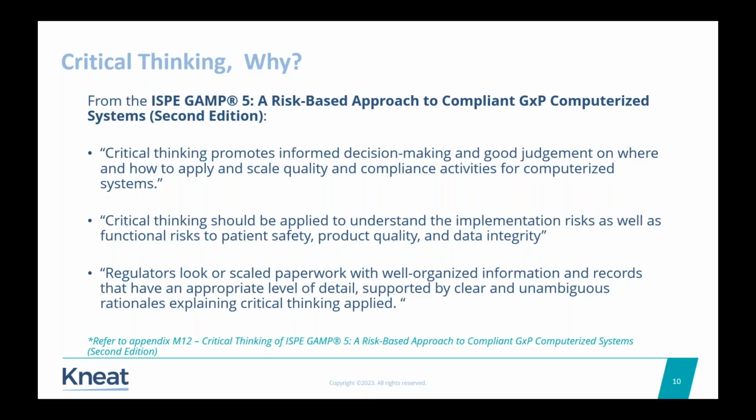Essentially, what this means is that you have thought about the process that this particular software system is going to help you implement. Where are the riskier parts of the system? How did I determine that this is a high risk feature or this is a high risk system versus this is a low risk feature or this is a low risk system? And can I stand over that? Can I stand in front of an auditor and say, yeah, we determined that this feature was high risk using these criteria that we've agreed in our company, and that followed the FDA methodology and the FDA guidance on CSA.